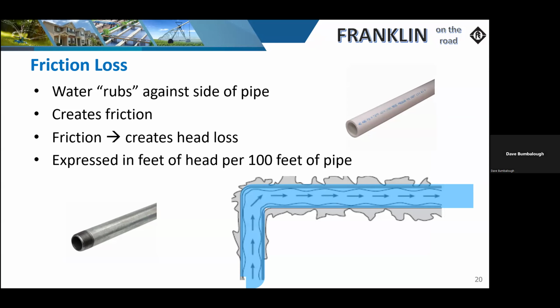The third function we have to look at is the friction loss. And this is where it gets a little tricky. I know oftentimes, if it's a standard pump that's being installed in the well, 1-inch pipe is typically what is used. As a manufacturer, and some of my early years were spent in an engineering lab where I tested and developed a lot of these products, the rule of thumb is whatever the pump discharge size is, that's what we're expecting you as a manufacturer to use when you're installing this.